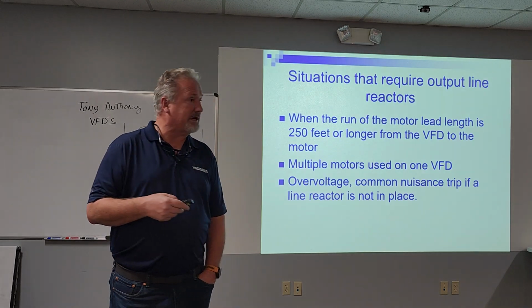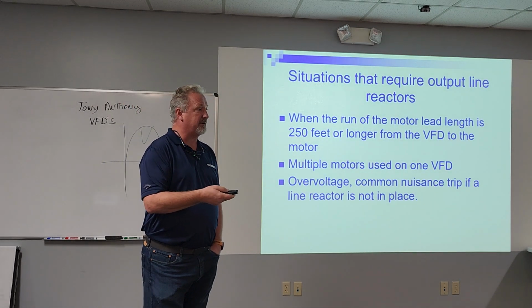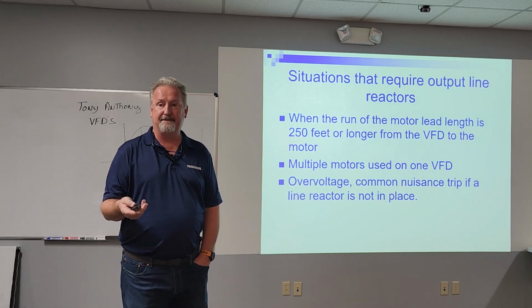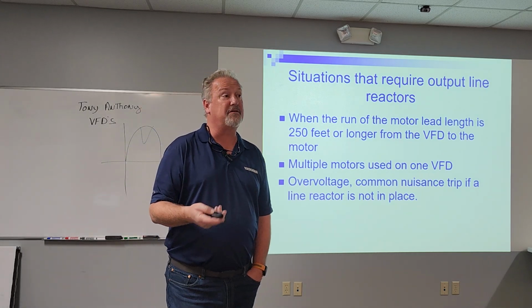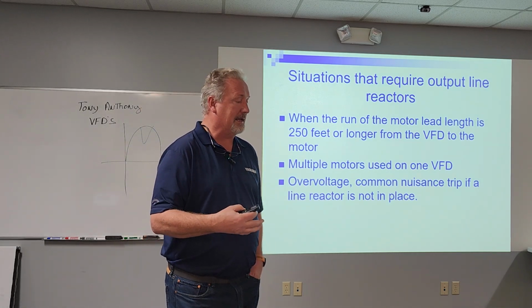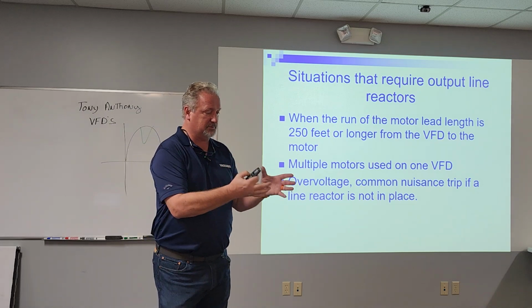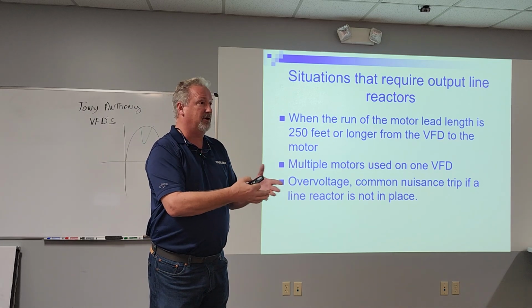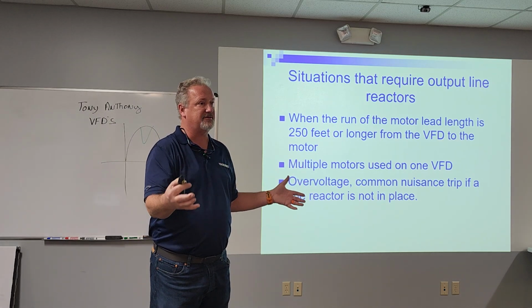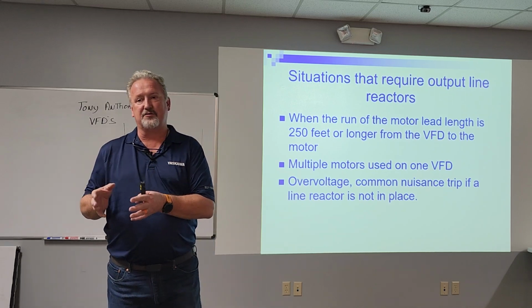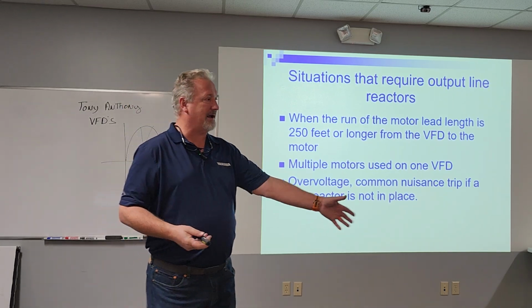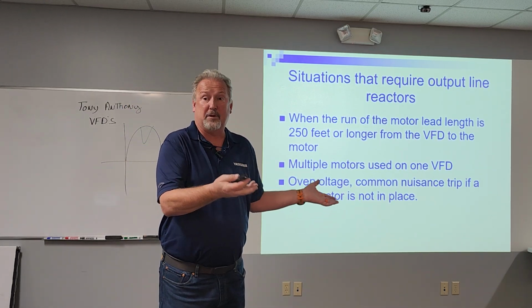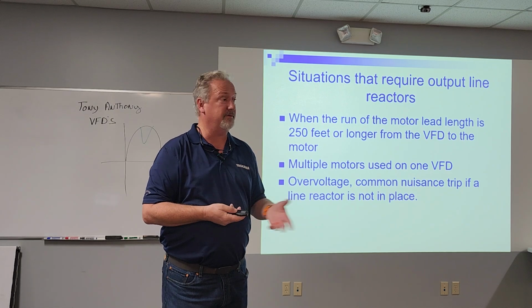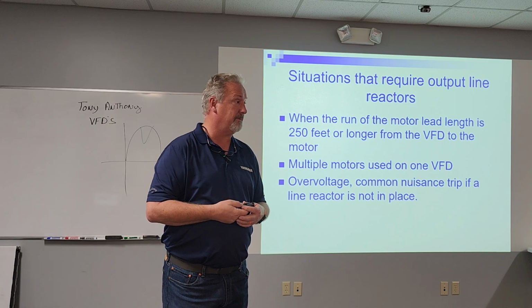Okay. So we can actually run this, and you'll see this on fan arrays. Do you do a lot with fan arrays here at all? We're starting to see this more and more on fan arrays. You can take one drive and run as many motors as you want, as long as you size the drive properly. Because to the drive, if you've got 4 10-amp motors, we just see it as one big 40-amp motor. We don't care. We put a 40-something amp drive on it, and we're good to go.